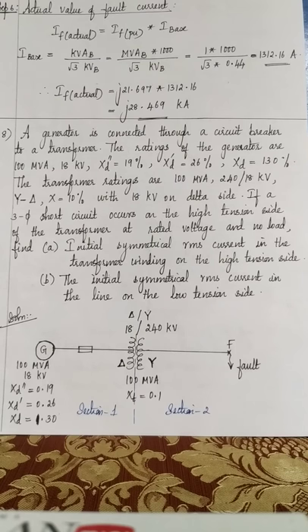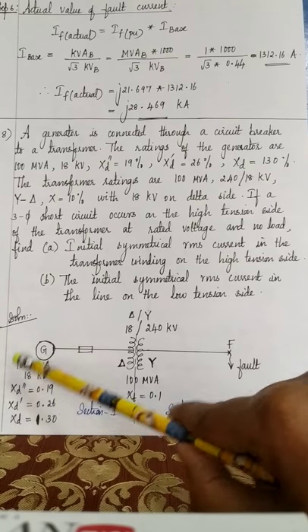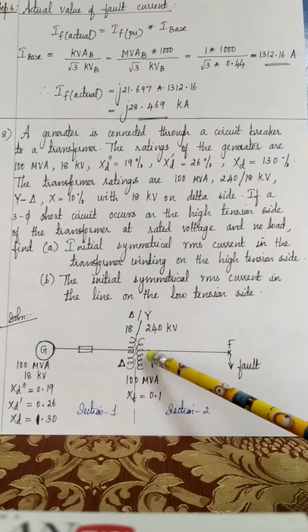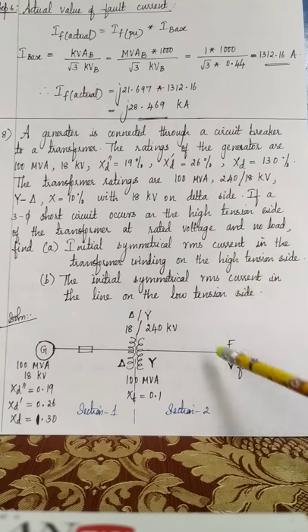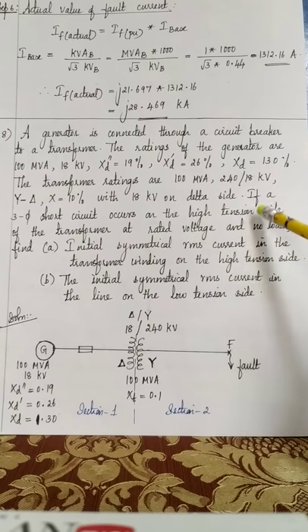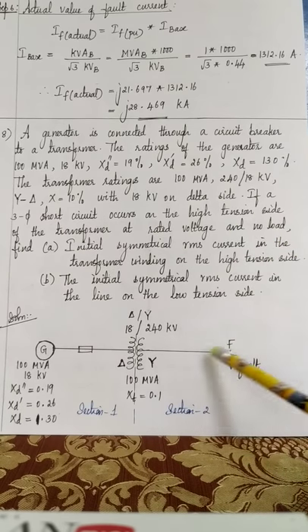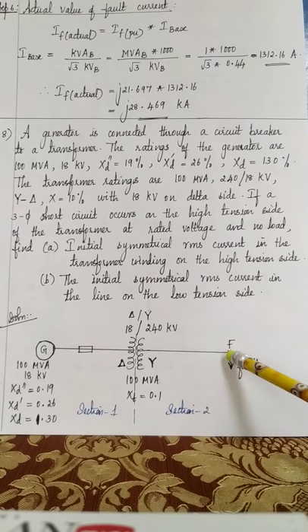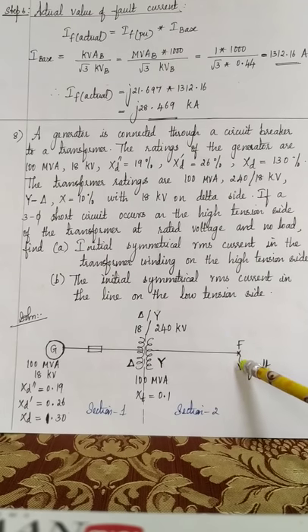Okay. So you have drawn the single line diagram. We have a generator with the ratings marked and a transformer. And somewhere after the transformer, on its high tension side, a three phase short circuit fault is occurring. So I have denoted the fault point as F. Okay. And here once again you have to note down that the generator or the power system network is unloaded. So what do we have to assume? Assume the pre-fault voltage at the fault terminals as 1 per unit. Okay. So the pre-fault voltage of an unloaded power system is assumed as 1 per unit.